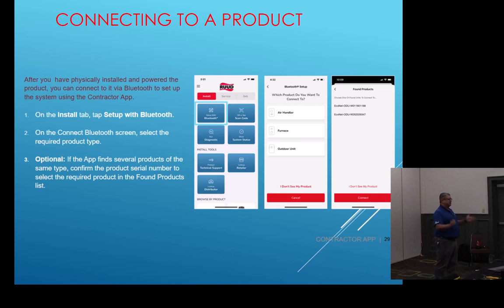I had this same situation happen. We had a 2-ton and a 4-ton side by side. The 4-ton was acting funky. I went out there. When I pulled this up, I had 2 serial numbers here, but they were the same serial number. Somehow the contractor had downloaded the 2-ton information into the 4-ton drive, and it was not working correctly. So we want to make sure that we select the right serial number on the piece of equipment that we're working with, okay? It's a little work. It's really simple, guys. So we just got to make sure that we're choosing the right thing and it works great, okay?